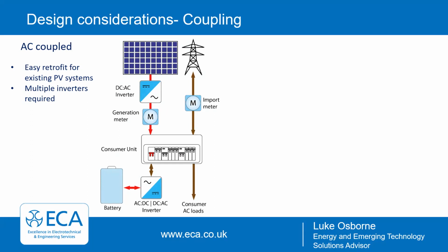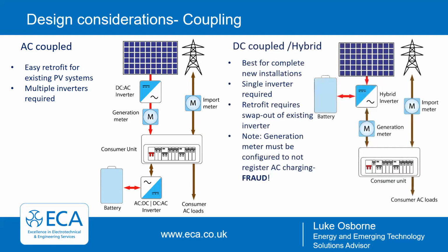So you've got the AC coupled side of things. If you're adding a battery storage system to an existing PV system without having to change the inverter, you can add on a new system with an additional inverter. So you've got the existing setup, which is converting the DC from the solar panel to AC to feed into the consumer unit, and then you've got a similar but reversed arrangement for the additional battery. It does mean having two inverters, so you wouldn't tend to specify this for a new system, but it's good for retrofitting to existing systems.